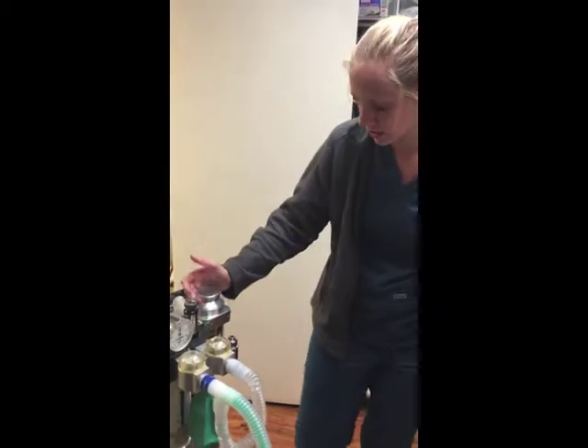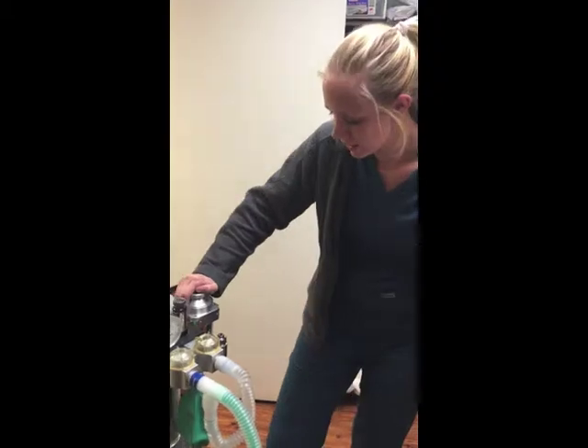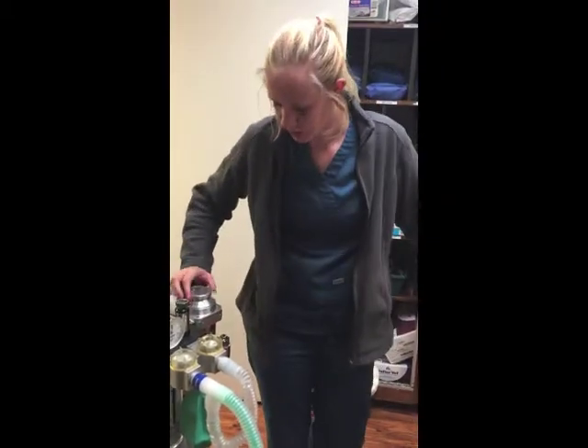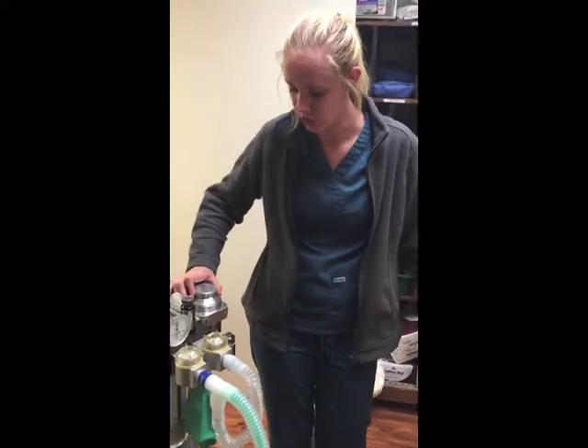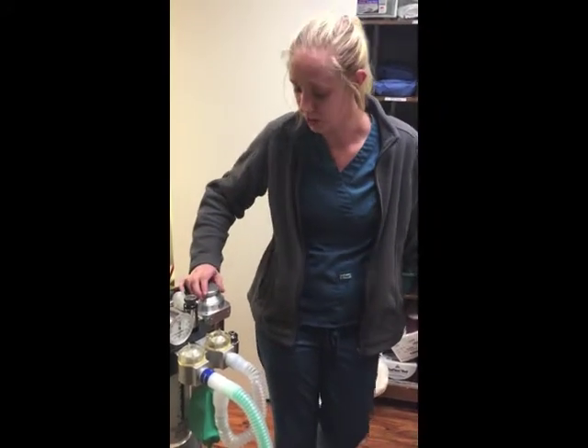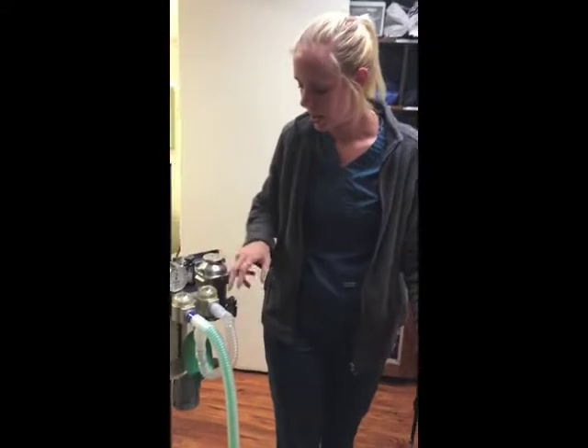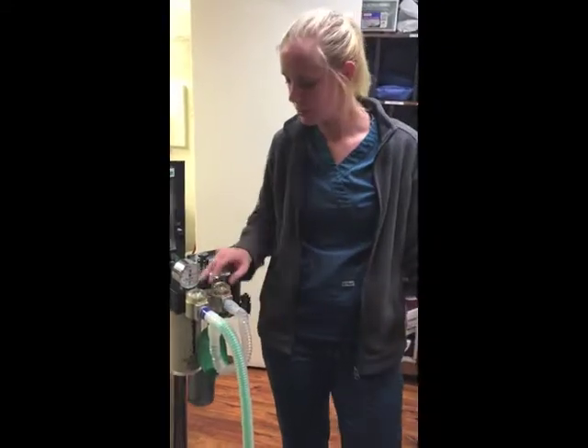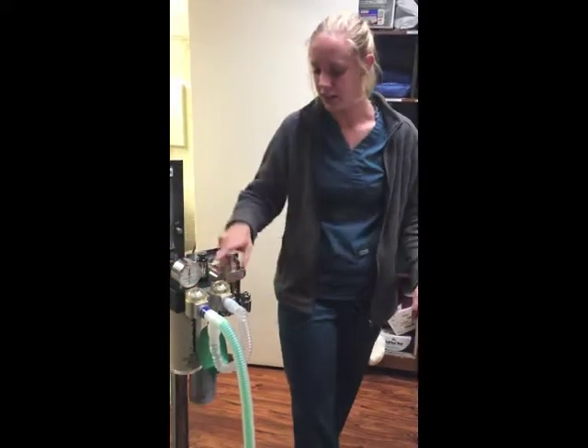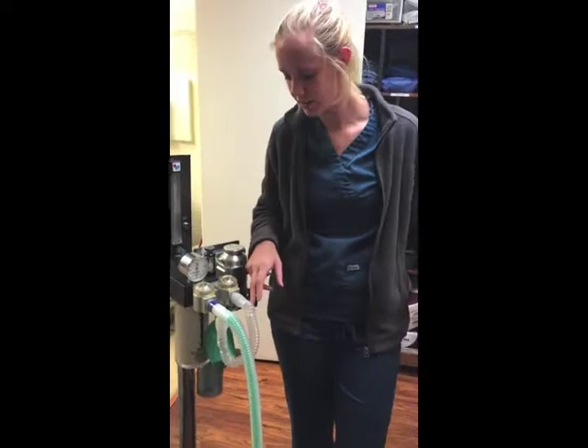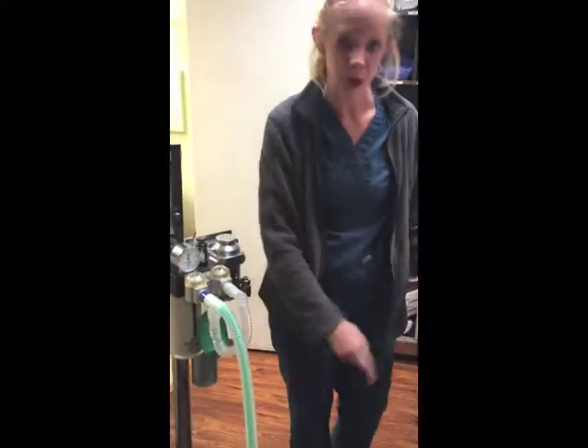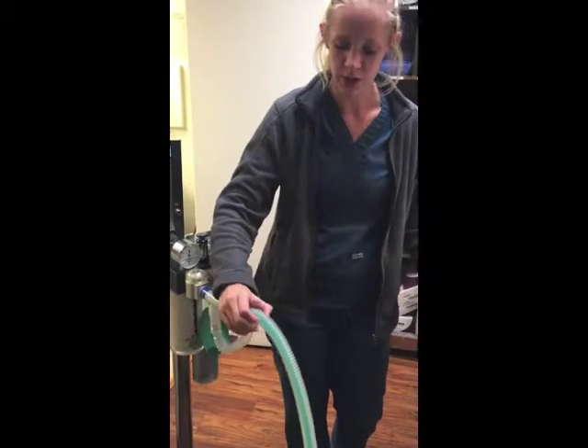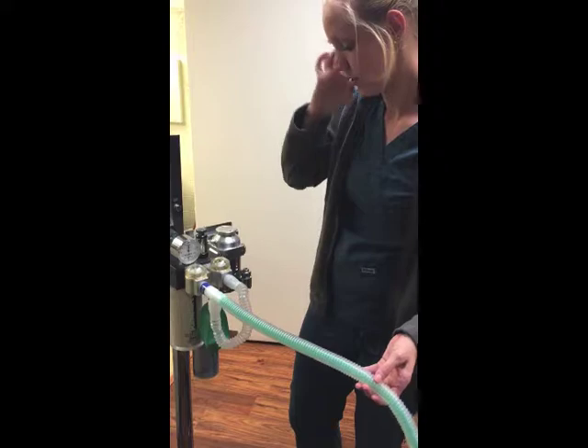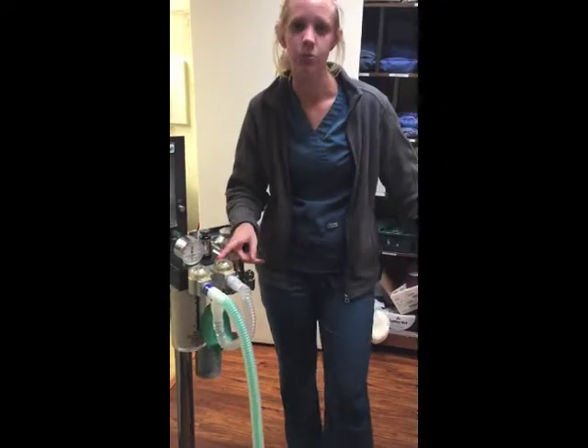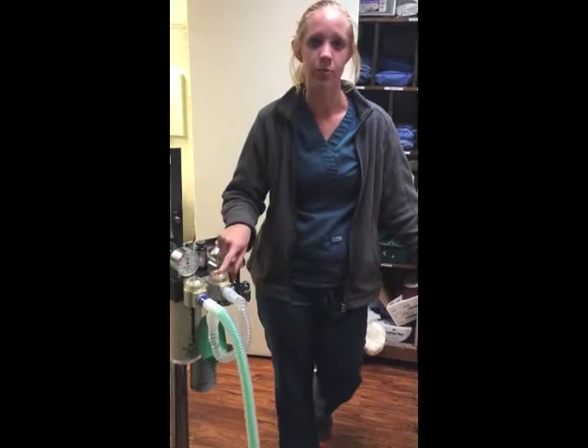This is our vaporizer. The gas that we use is isoflurane, and its function is to allow so much ISO to control how deep we want the patient to be during anesthesia. If they're too light, we can turn it up, or if they get too deep, we can turn it off or just lower it. Whenever air is being moved through the tubes, it goes through the inspiration valve and the expiration valve, depending on whether the animal is inhaling or exhaling. When they're inhaling, they're pulling air from the tube into their body, and then they exhale back into the external tubing. These flutters will move whenever the animal is breathing, so you know that they are breathing correctly.